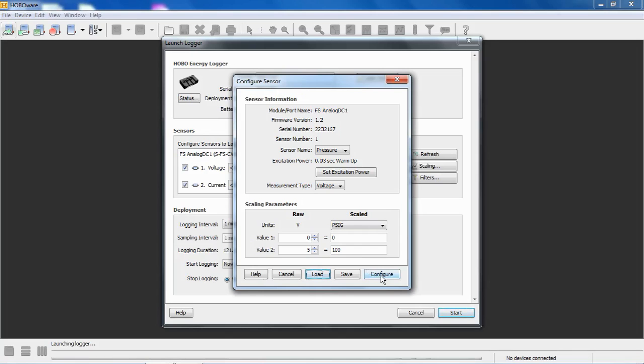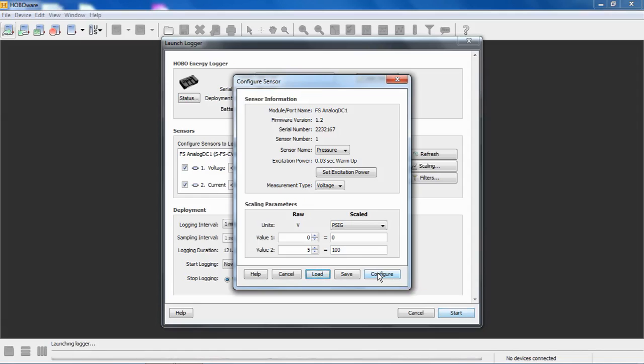If we click on configure right now, this configuration will be sent to the analog module, and it will be stored in it. And these modules, both the TRMS and the analog module, include technology that makes this configuration sticky. In other words, when I send this configuration to the module, it's written into this module, and it stays in that module until it's reconfigured. So the module can, once it's configured, can be removed from the logger, put in a different logger, and retain its configuration.